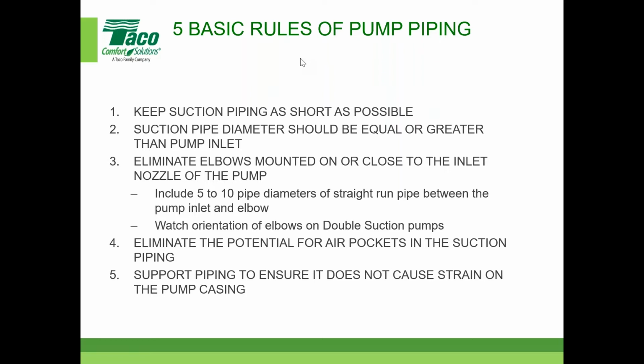Eliminate the potential for air pockets in the suction piping. Air and dirt are deterrents to HVAC hydronic pumps, so if you can eliminate air pockets, ups and downs and whatnot, that's very, very important. I can't stress that enough. And then support the piping. The pump cannot support the piping; it's going to put strains on it. We have pictures. You walk into a room and you can tell: the flexible connector's twisted or whatnot. The pump is not designed to support the piping, so you need pipe hangers properly mounted to take the strain off the pump casing.